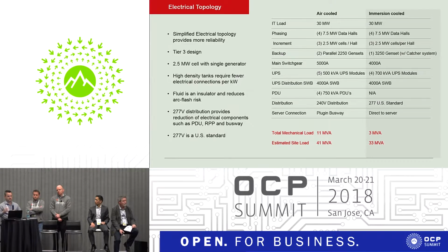So we get into the electrical topology. There's a lot of comparison here that you can read through. The two big takeaways I want to point out to folks here is, one, the reduction that we have in the electrical demand because of the mechanical system change, getting rid of all the compressorized equipment. We went from a mechanical load estimated of 11 MVA for the 30 megawatt down to 3 MVA. So not only is that a tremendous savings in CapEx, there's a lot less space required for that electrical infrastructure and distribution.